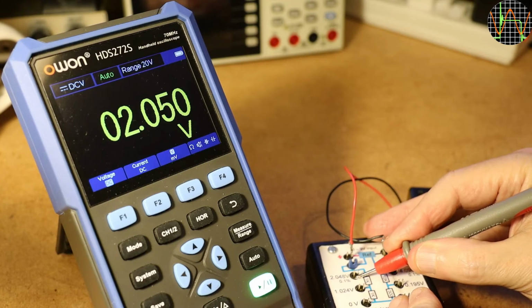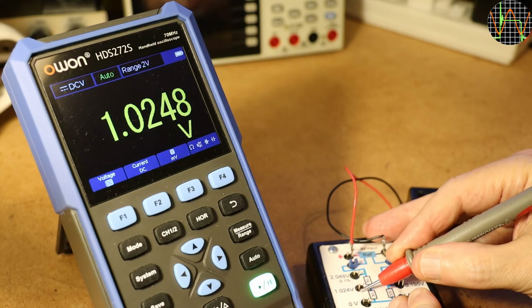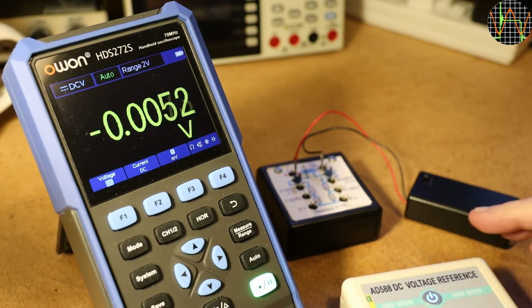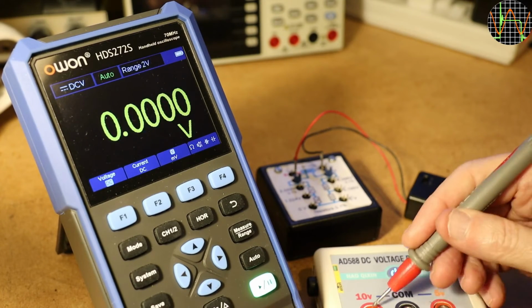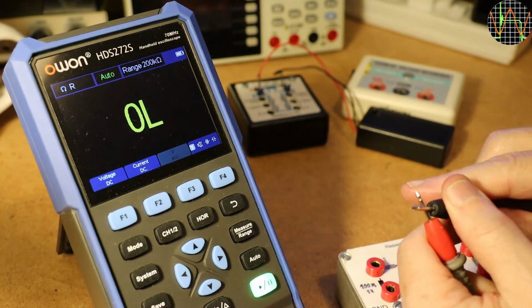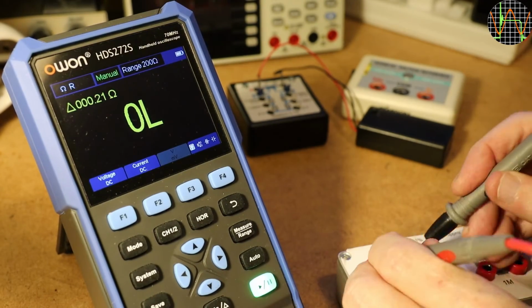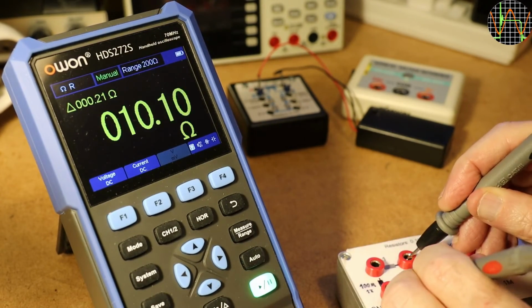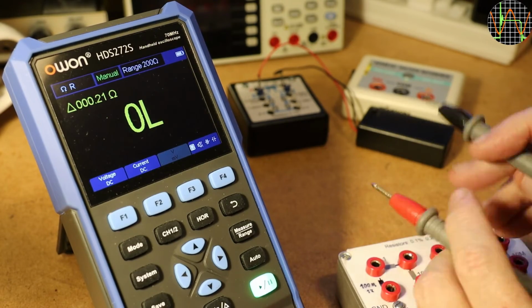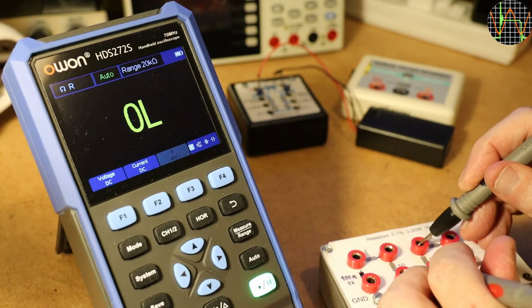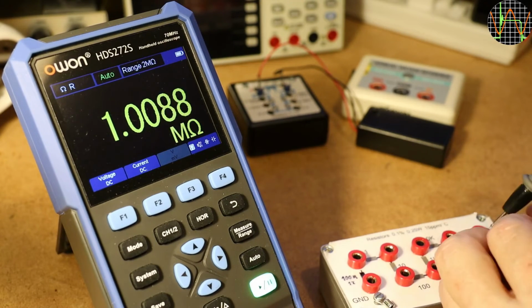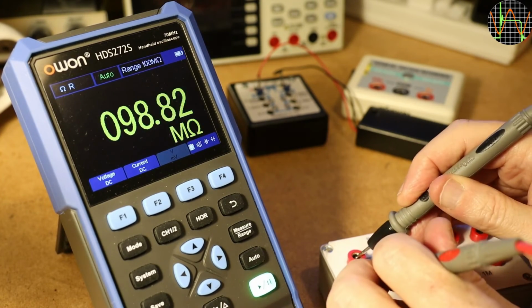I tested DC voltage against various voltage standards I have, and results were all within spec, which is plus minus 0.3% plus 5 digits. Resistance against my 0.1% references was also okay. The meter has a good rel mode for very low resistances, and auto ranging is quite fast. Having a 100 megohm range is nice.